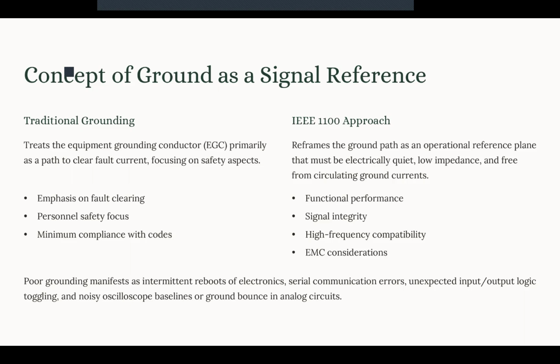So IEEE 1100 takes another approach. It reframes the ground path as an operational reference plane. Based on IEEE 1100, that ground path should be electrically quiet, so it has minimal transient noise. It should have a low impedance across both power frequency and high frequency, and it should be free from circulating current, because circulating current can cause voltage offsets in the system.